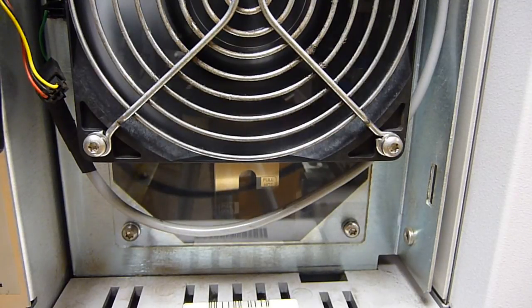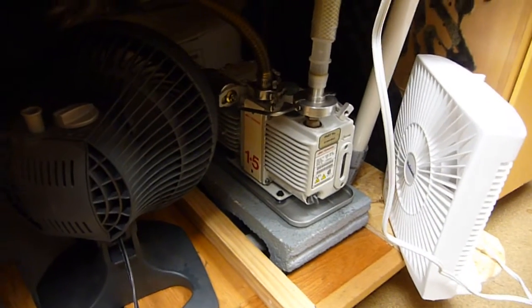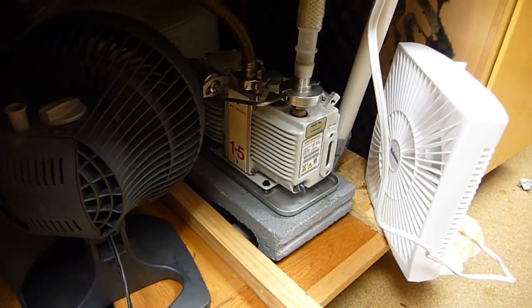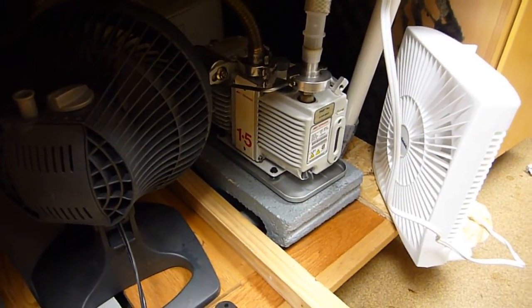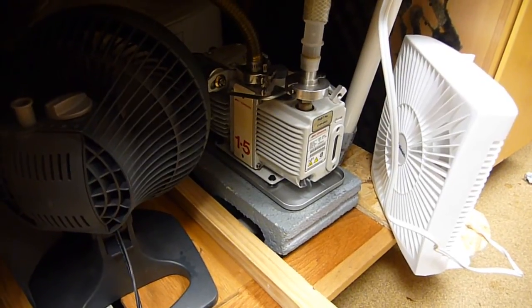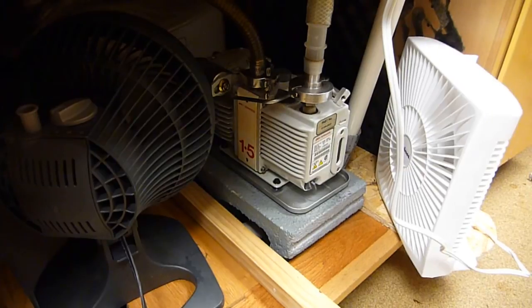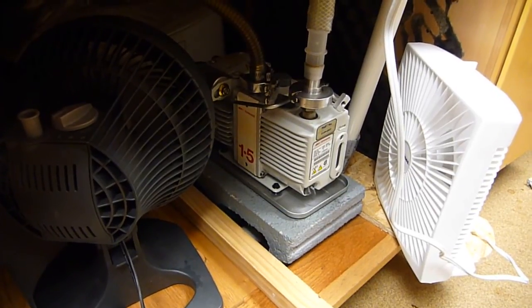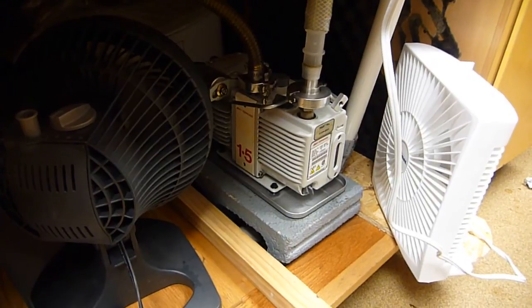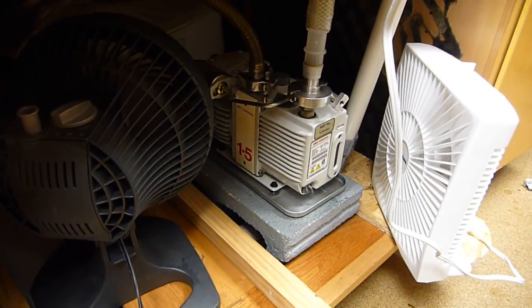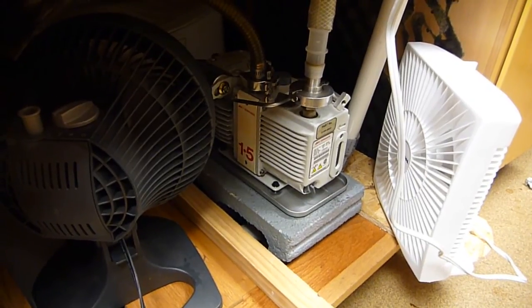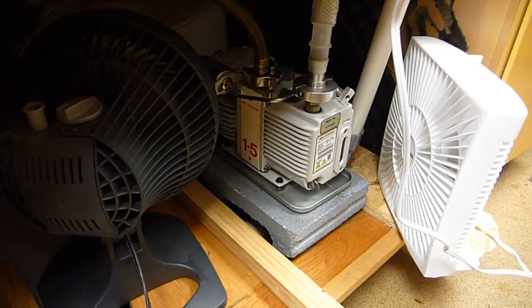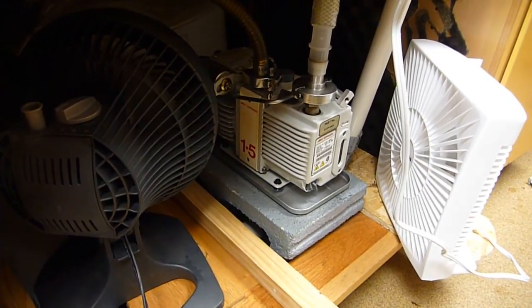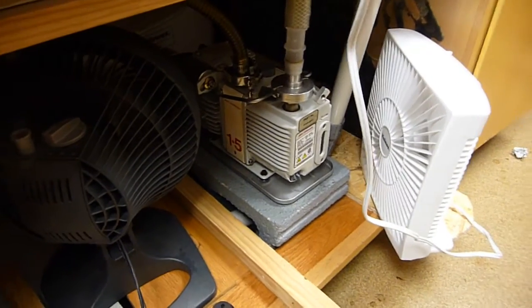And these are some of the tricks we employ. Trick number one, we have the rough pump separated a goodly distance, roughly 6 to 8 feet of tubing away from the GC mass spec system. This way, if the diffusion pump sucks back any of the rough pump oil, it has a long way to go, and it's unlikely to contaminate the diffusion pump oil with rough pump oil.